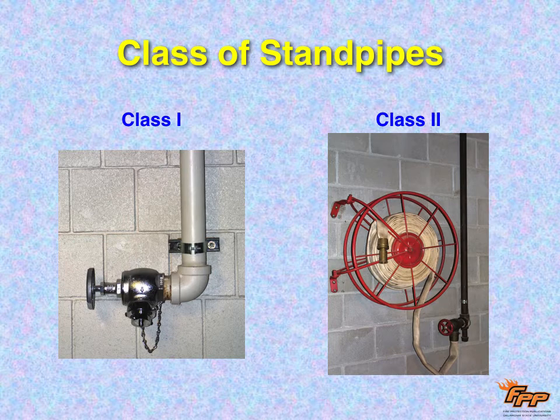They're usually going to have a 2.5 fitting with a fitting that takes it down to 1.5 inches, and they'll have a cover on them. So there are procedures to using these; you want to use it right and set it up right. Class two is for occupants, and it has pre-connected hose, pre-connected nozzles. A lot of times these nozzles get stolen, though. They're much less reliable. Sometimes the hose is a little questionable, might be deteriorated or rotted. So firefighters usually don't use these. They're very unreliable. We'll use them if we have to. If it's life or death, you might want to try and use one of these, but we would much rather use our own hose.